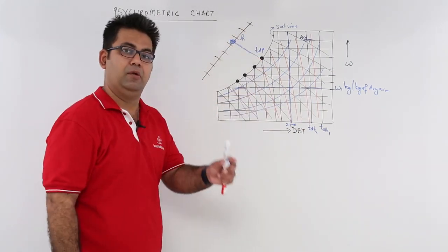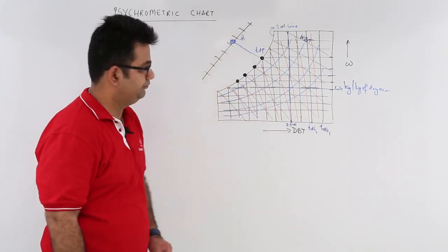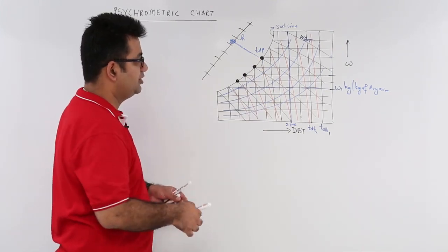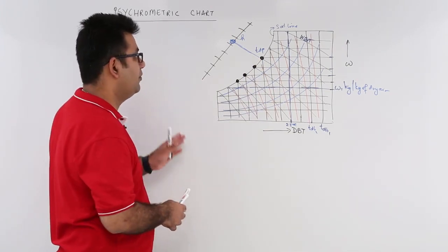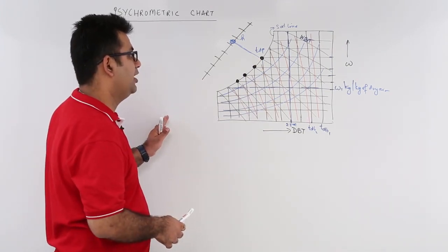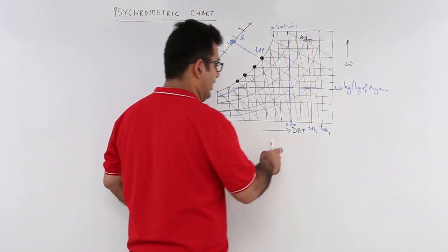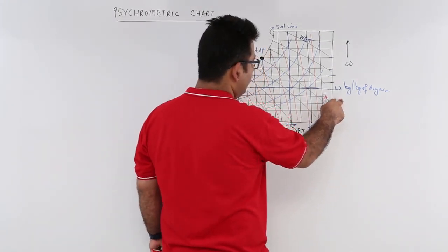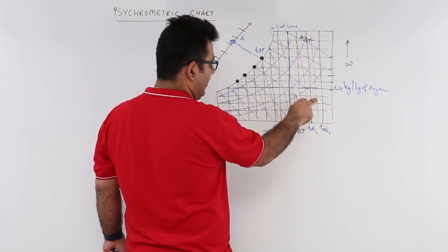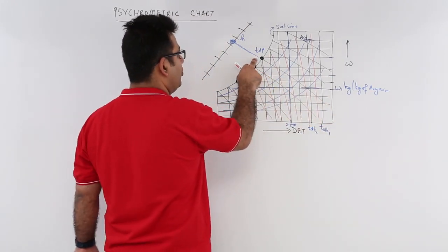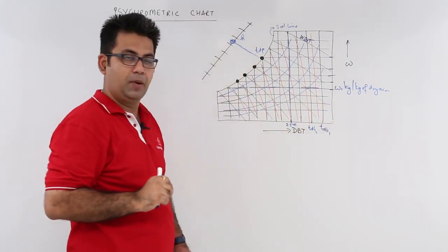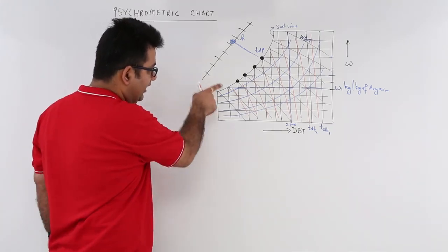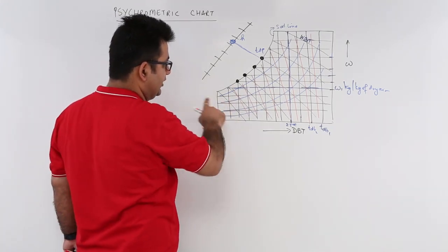When you extend the wet bulb temperature line and cut this outer axis, that point shows the enthalpy value at that particular condition. So the psychrometric chart tells you the dry bulb temperature, the specific humidity, the wet bulb temperature, the dew point, and the enthalpy.